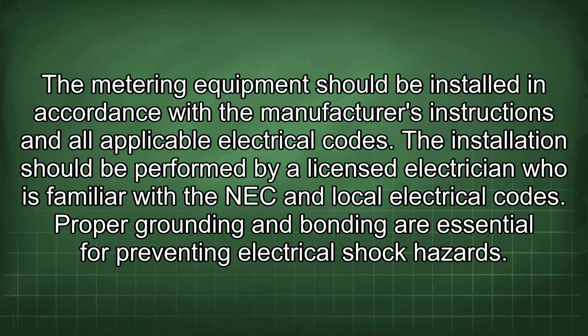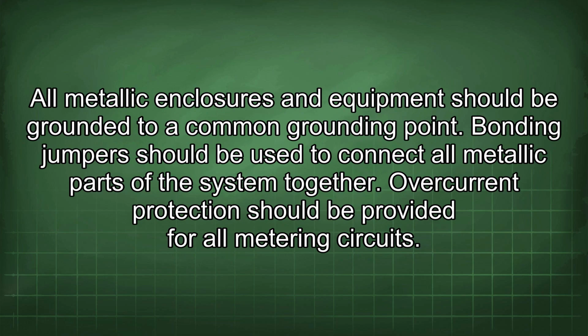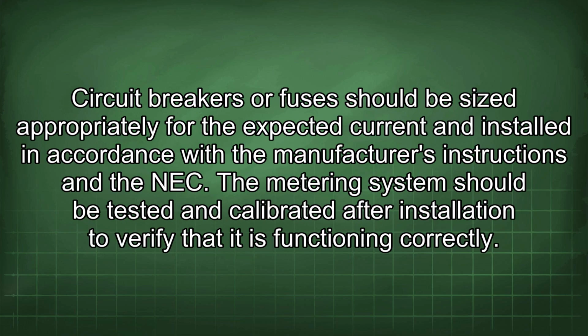Proper grounding and bonding are essential for preventing electrical shock hazards. All metallic enclosures and equipment should be grounded to a common grounding point. Bonding jumpers should be used to connect all metallic parts of the system together. Overcurrent protection should be provided for all metering circuits. Circuit breakers or fuses should be sized appropriately for the expected current and installed in accordance with the manufacturer's instructions and the NEC. The metering system should be tested and calibrated after installation to verify that it is functioning correctly.